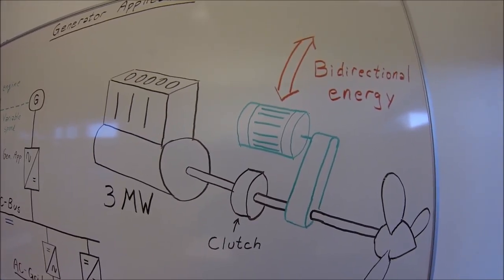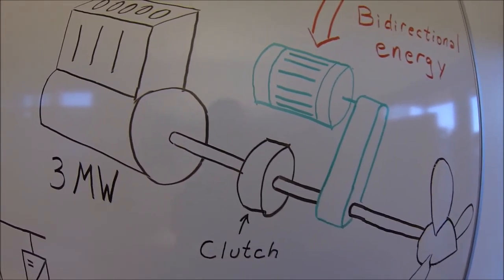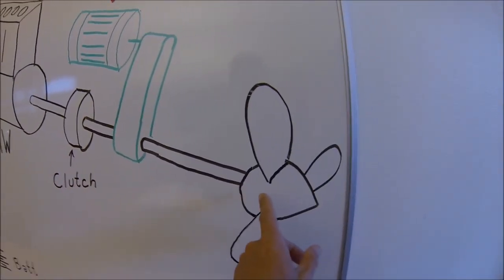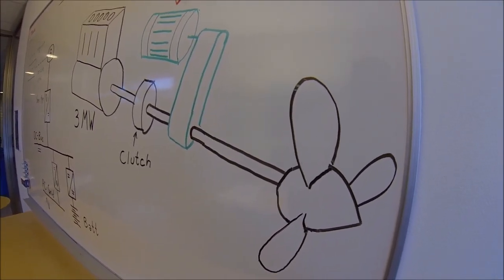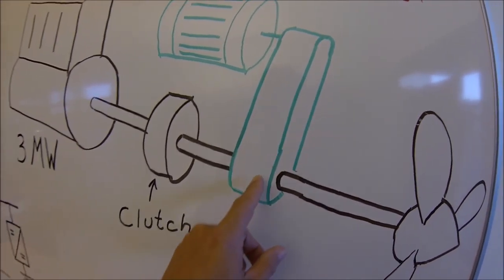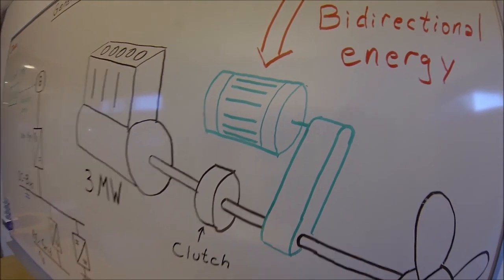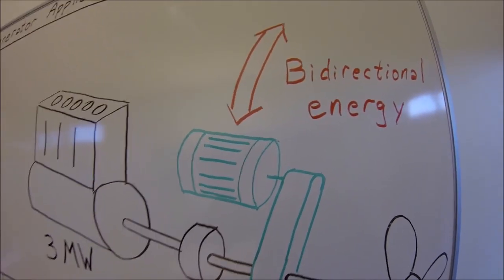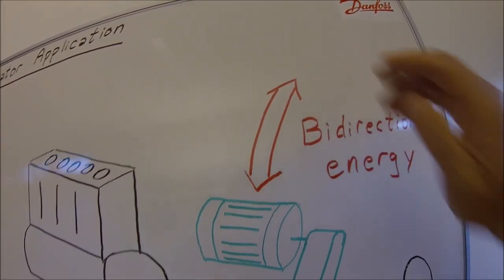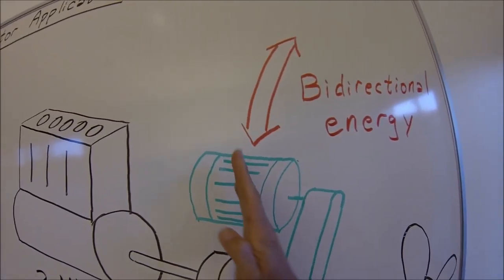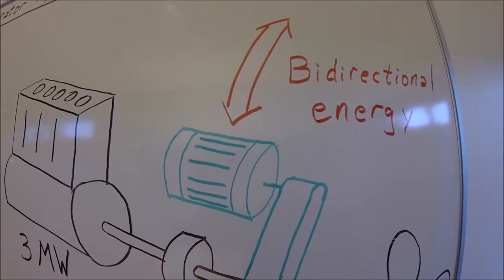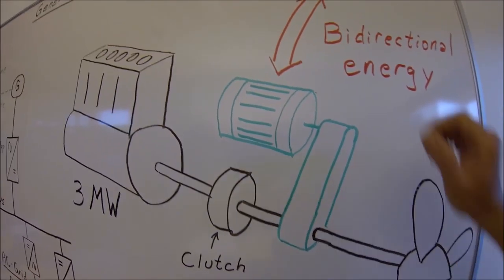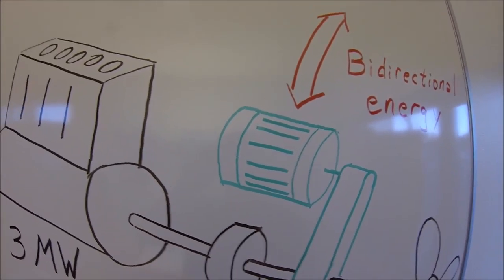Typical installations are shaft generators. It could be a big diesel engine on a ship which drives the propeller shaft and the main propulsion units. There could be a generator connected to the shaft, and this shaft generator can with this application be used bi-directionally. That means you can extract energy from the generator, but you could also add mechanical power to the shaft by using the generator as a motor.